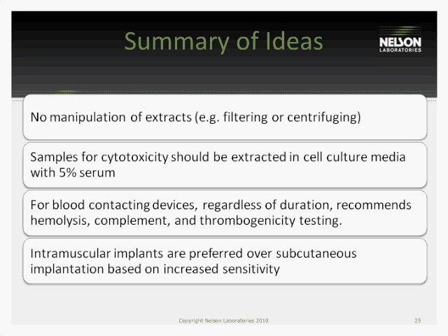When you're looking at the next category, the blood contacting devices, this is an old feeling from the FDA. We are actually looking at rewriting ISO 10993-4 to try to incorporate some of this. And in fact, one of the authors of this document, Jennifer Good, is on the -4 group that is helping us write. But it's stated in there that for blood contacting devices, regardless of duration, they want you to do hemolysis, complement, and thrombogenicity testing. Now we're going to talk a little bit in the justification section on how to maybe look at justifying out of those tests, but right now that's the statement.